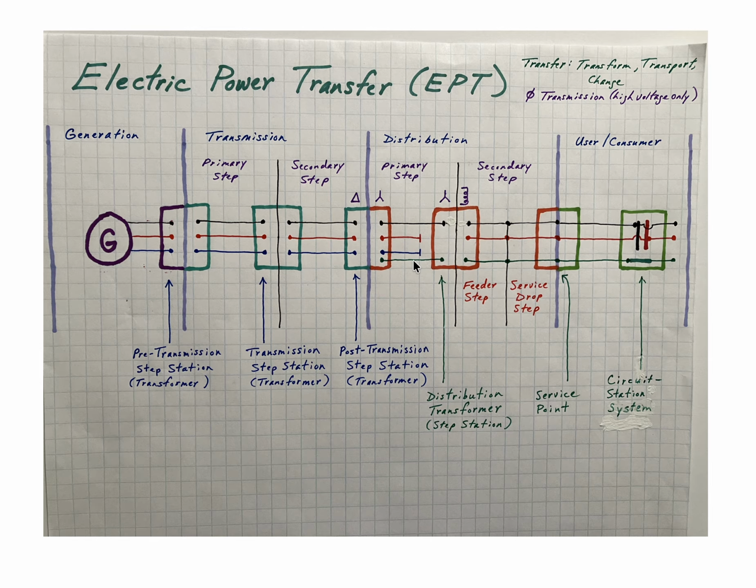These 2 neutrals are not physically connected in the transformer. The only way they're connected is they are connected to ground somewhere, and that's only for safety reasons. So then finally you have a service point. That's really just kind of a splice, a connection of your cables and conductors up in the air. And it's not really a box or a transformer. It's just a point. It's a very critical point in the system. So that's your service point.